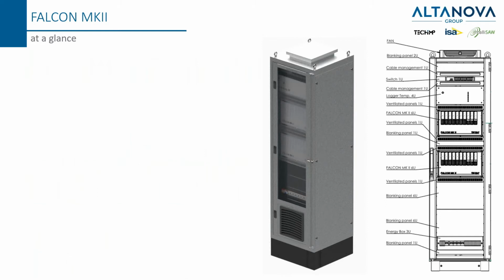This is an example of the system, how it appears on a real installation. There is a cabinet where there is a switch to connect all the units and have an easy interface for the center. The Falcon Mark II and the data logger also. Plus, of course, the power supply to provide power to all the units inside the same cabinet, the fan also for cooling the system, and this is Altanova designed for a real installation at the substation.